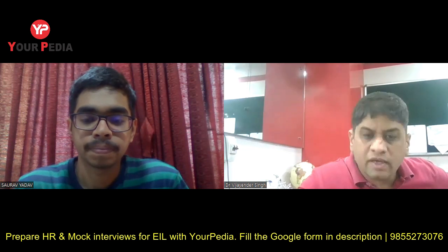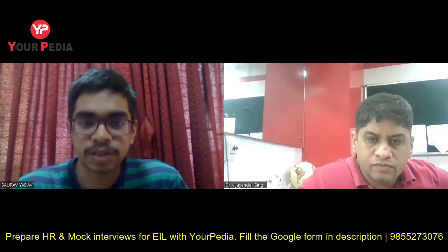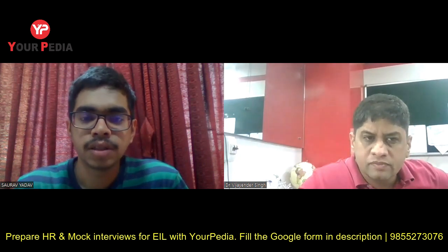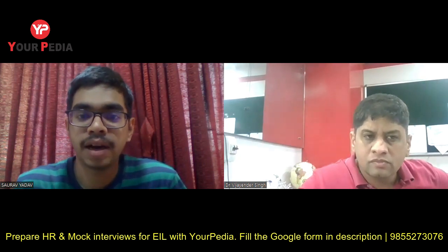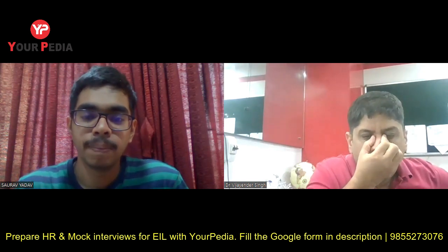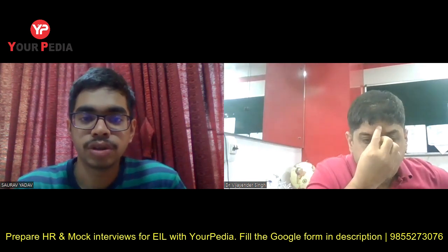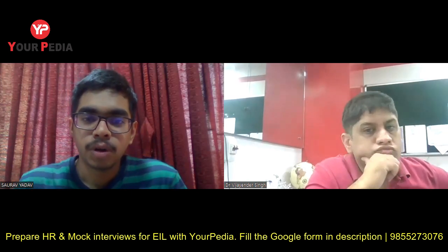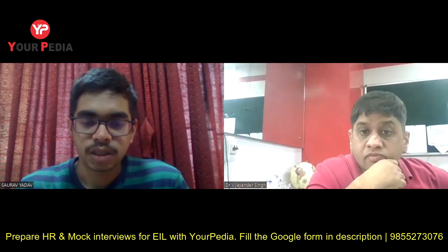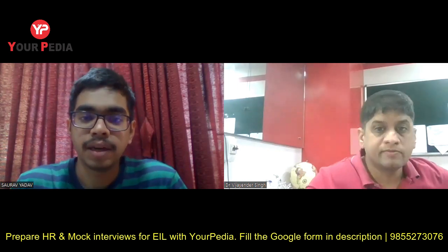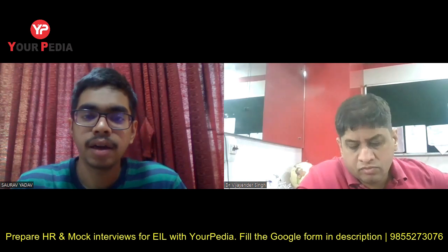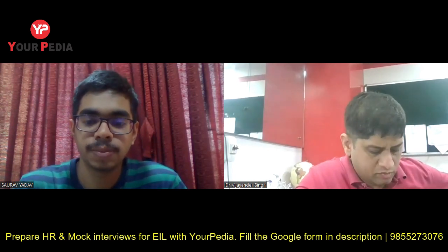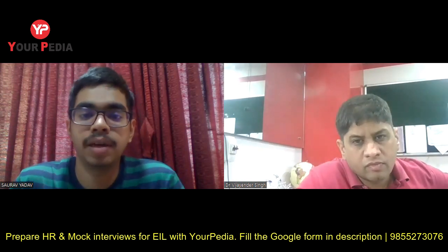Okay, so if I give you Himalayan river, which turbine will you put in that? Yes, sir. Since in Himalayan river we have a very high head available, the impulse turbine is more suited for the same. Why impulse turbine? Because if we see the specific speed of the turbine, then the higher head and the lower discharge conditions correspond to a more efficient generation as per the Himalayan conditions and the impulse turbine.